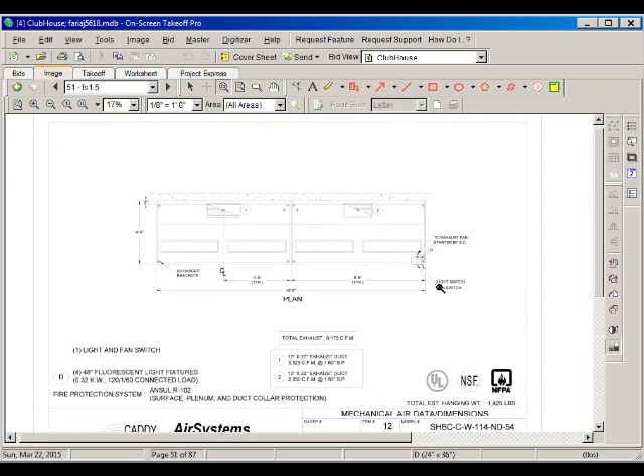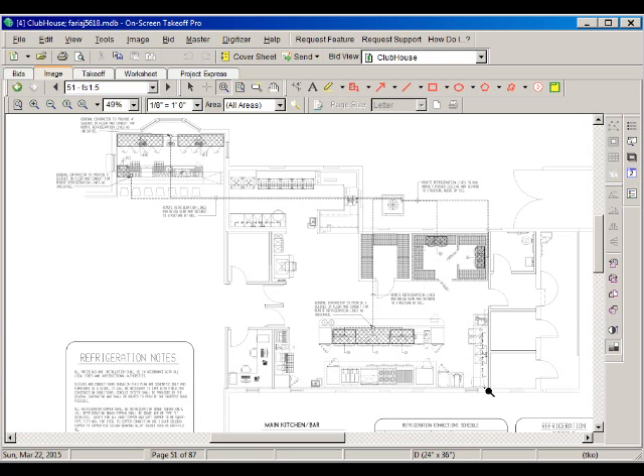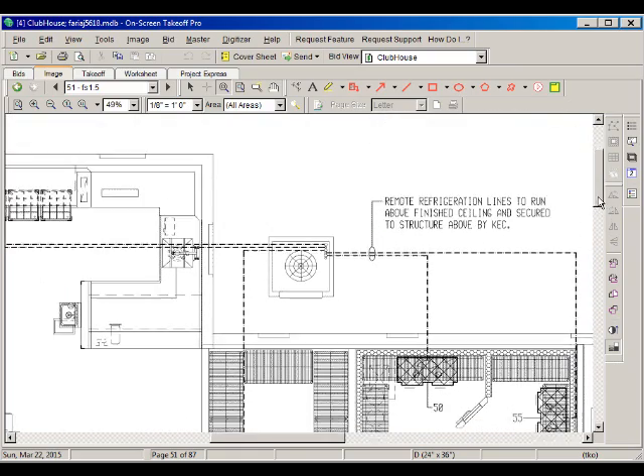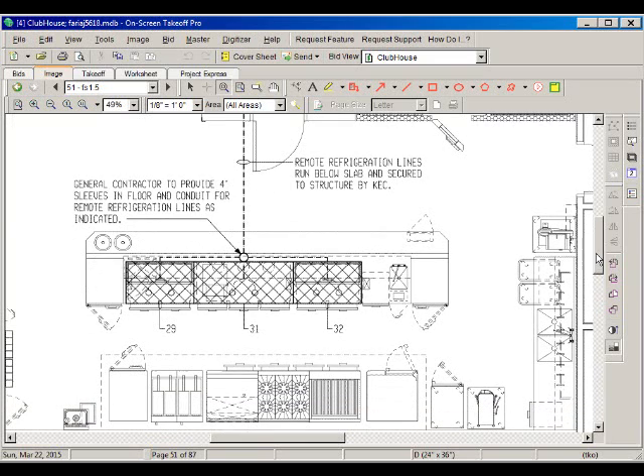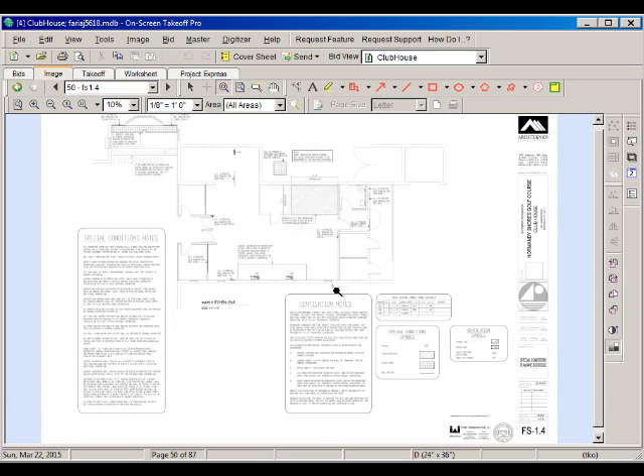Very likely it's going to be connected to the exhaust hoods because that's where the grease is caught from the cooking operation. When they cook, those greases are caught in the hood and the potential is for the high heat to make those greases catch on fire. So then they will start a fire. Some sensors in the system would trigger an alarm and then the fire suppression system should kick in and turn off the fire.